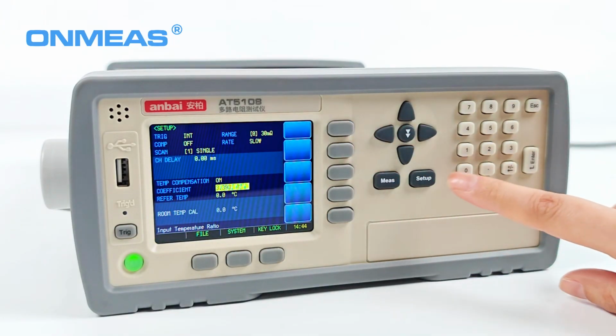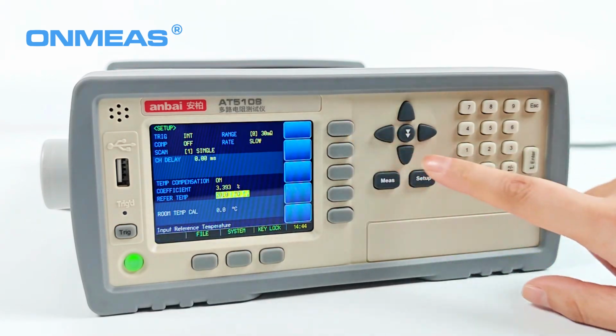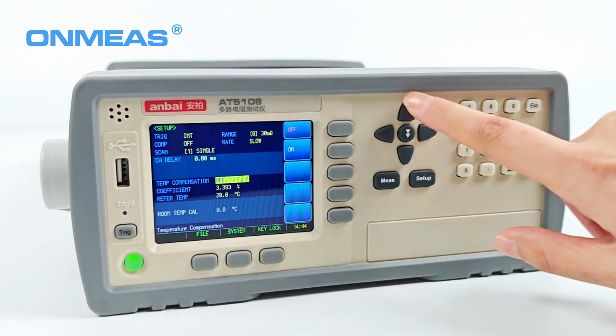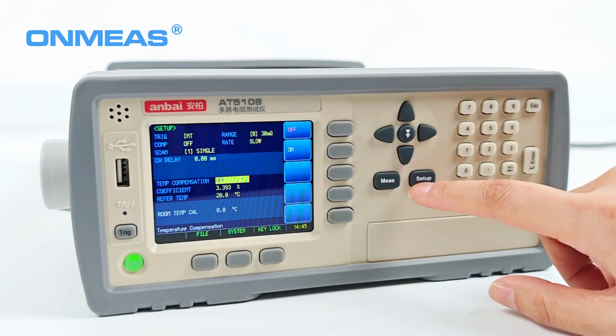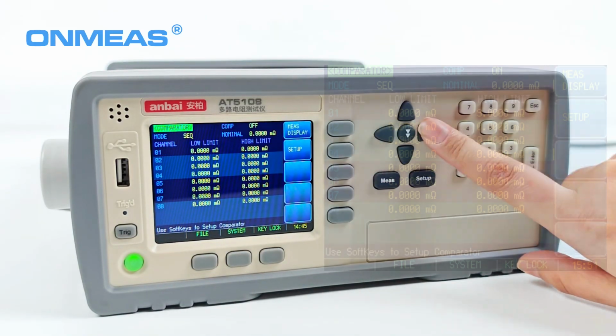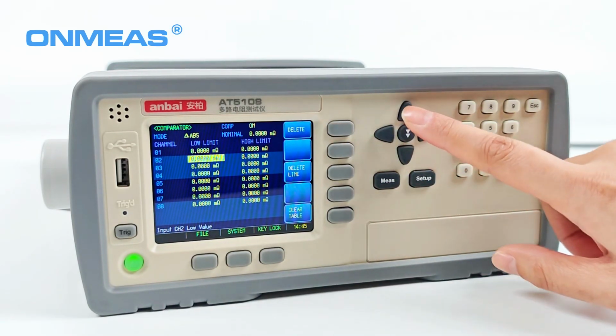Temperature compensation requires setting the temperature coefficient of the material. The measured result reflects the value at the reference temperature. Press the Setup key, then press the Comparator Settings function key to open the Comparator Settings page. The comparator can set the upper and lower limits for all channels.